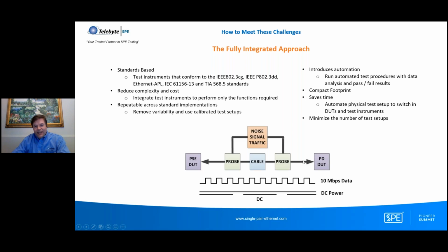We'll try to integrate as much functionality into the equipment as possible. So if an instrument could measure current or voltage and we can use that in multiple tests, then we need to try to implement that. We try to remove variability and use calibrated test setups whenever testing, so that you have valid test results. And then, as much as possible, it's nice to automate this so that there isn't any test that's user dependent, that may be hard to reproduce with another person or at another site. And we'd like to try to compact that and do our data and power testing with a setup where we don't change the setup as much as possible.